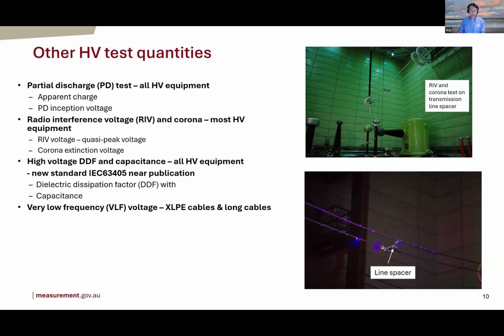Another fairly new type of test is a very low frequency, which is not often seen in the low voltage field, 0.01 Hertz, 0.1 Hertz. It is for testing plastic cables, cross-linked polyethylene cables, because they don't like DC. And you can't drive the cable with AC because they have high capacitance, and also long cable. Okay, so these are the quantities. This is nowhere near everything we actually need, but this is the majority of the quantities we need to test.